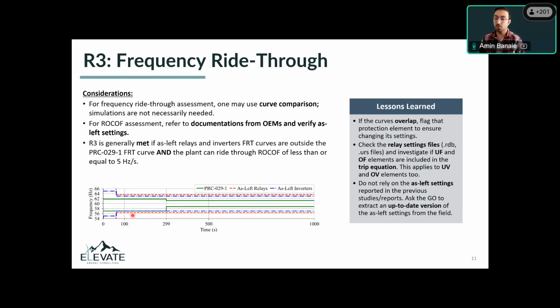But how we see it is that we want to flag this and ask the generator owner to change that relay setting, because there's always a small possibility of measurement error, and this can shift this curve inside PRC-29, and then that's going to cause the plant to trip. So we want to stay away from that. That's why we want to highlight that in our studies.